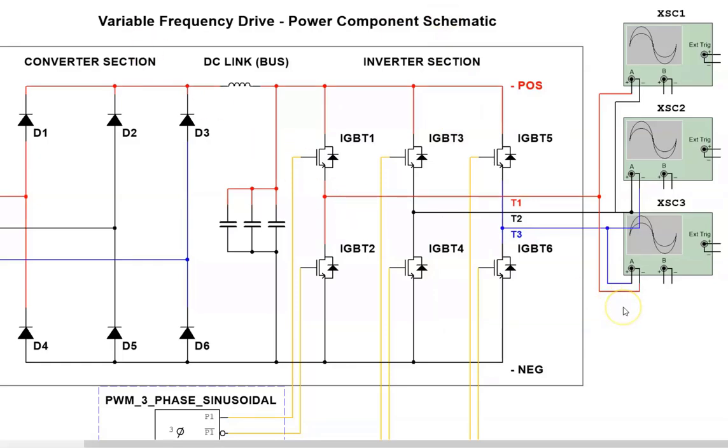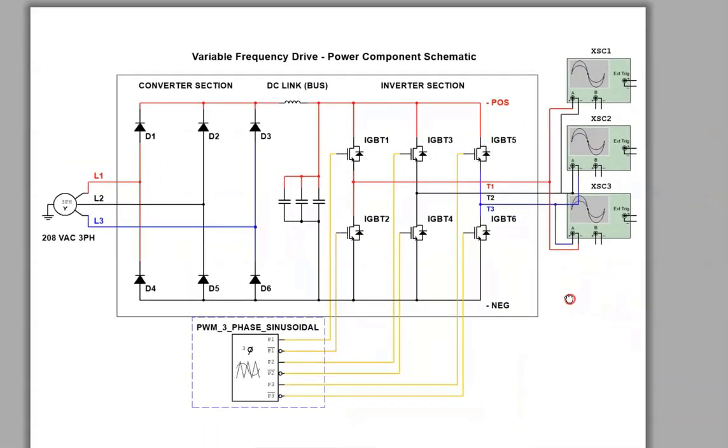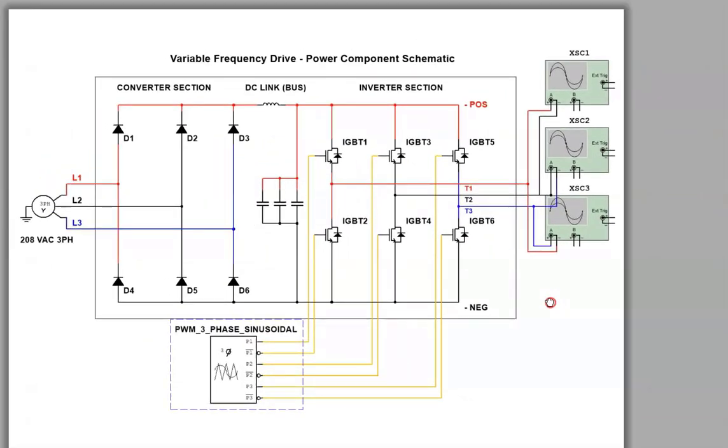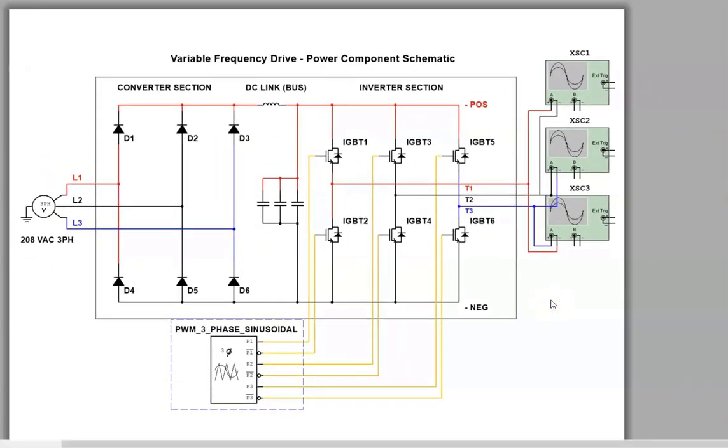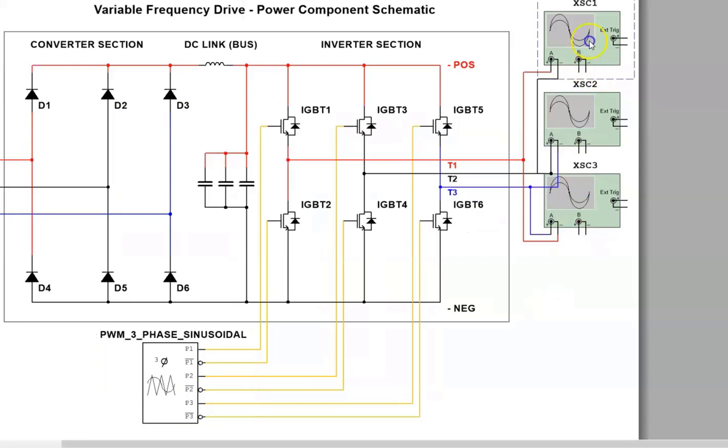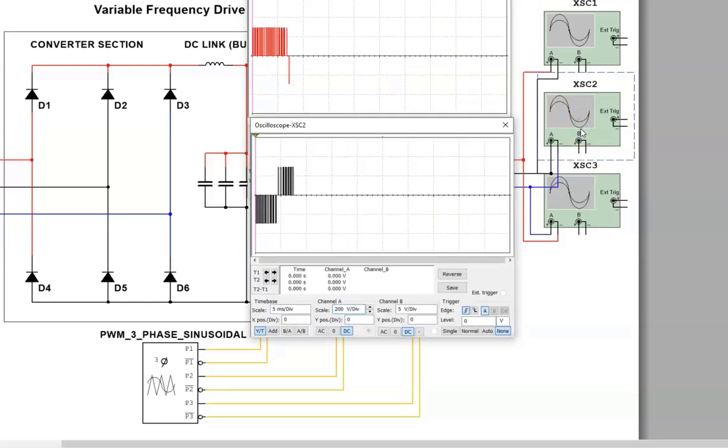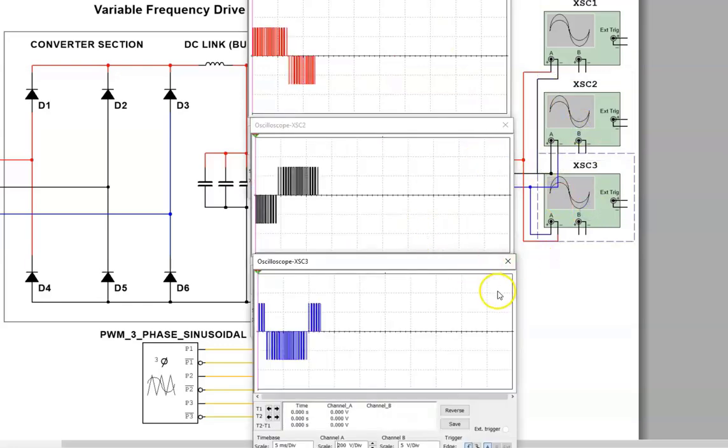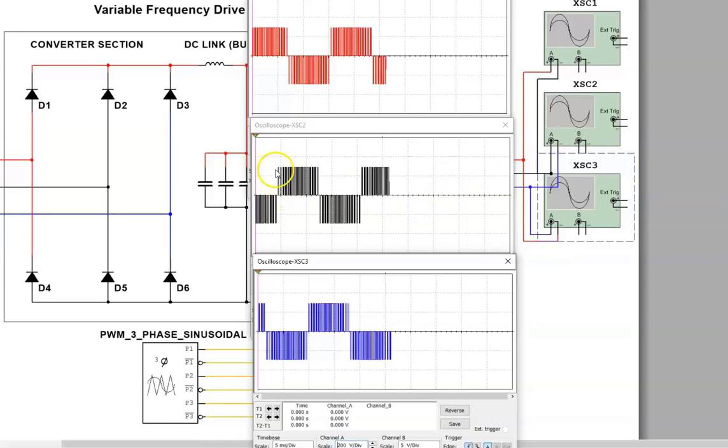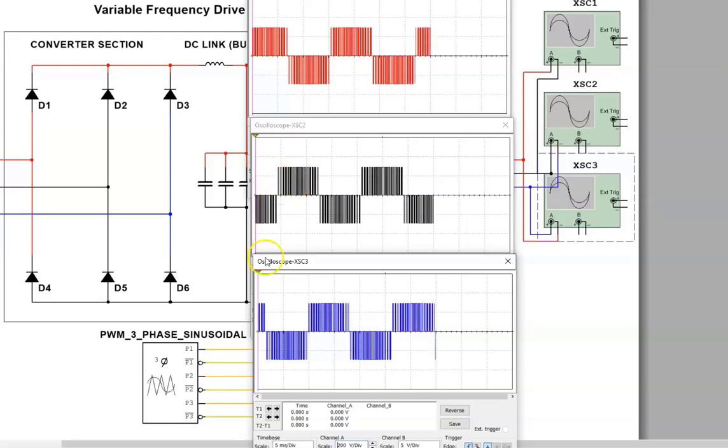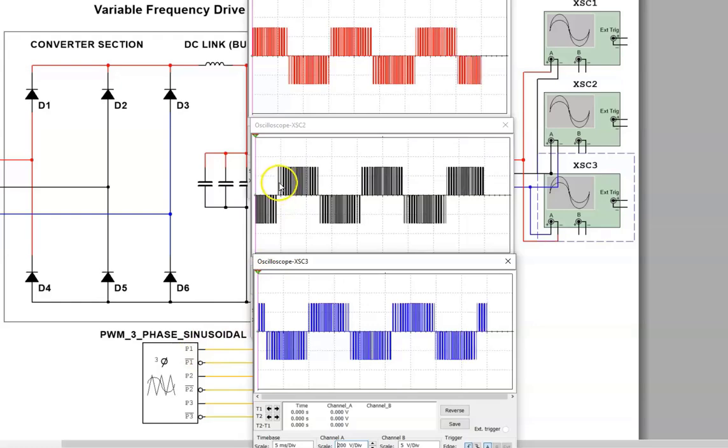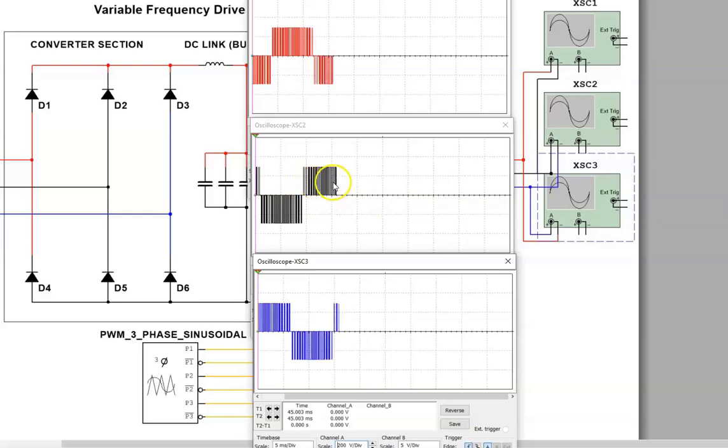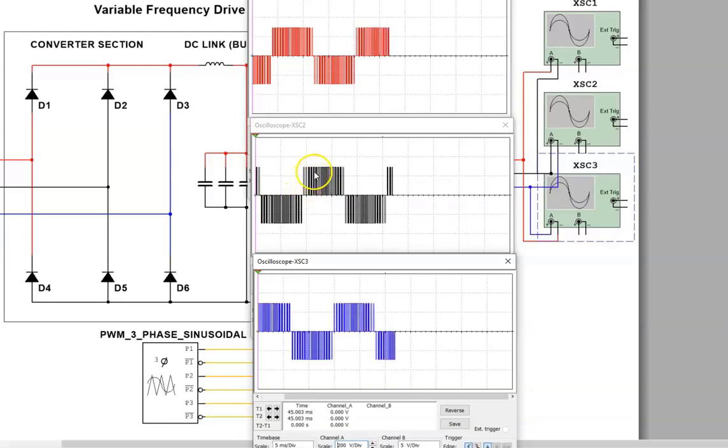So what I'll do now is I will run the oscilloscopes. And we have phase A running and phase B and phase C. Now, if you look at the output, if you can zoom in, you will see that there's pulses of voltage or slices of voltage. And the controller, the sinusoidal controller creates this PWM. And the width of those pulses determines the average voltage that's applied to the motor stator leads. If you were to measure each one of those and plot those values on a chart or in some graph paper, they would end up looking similar to an AC waveform.